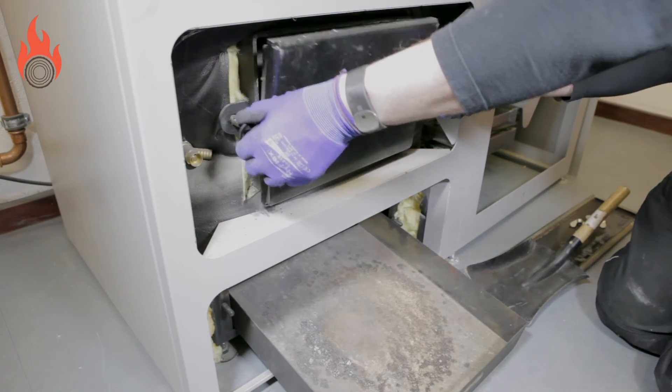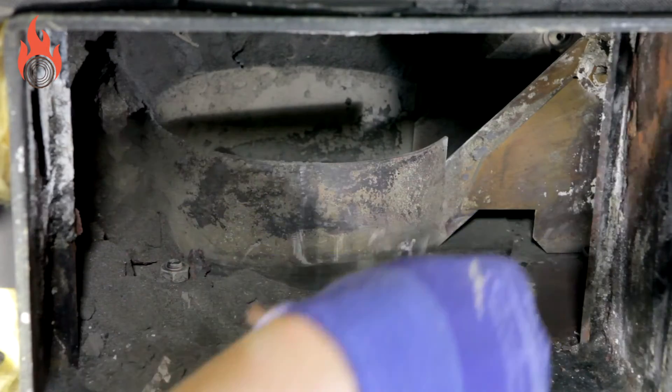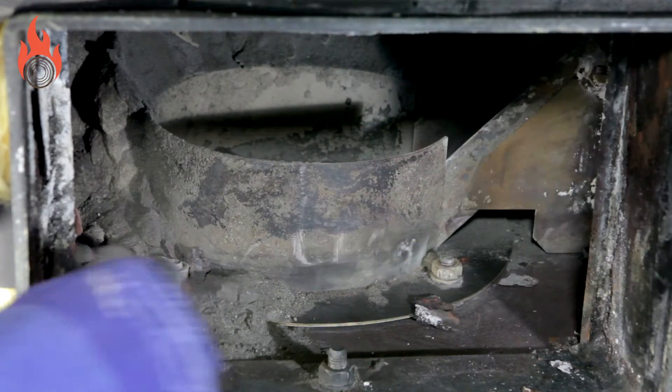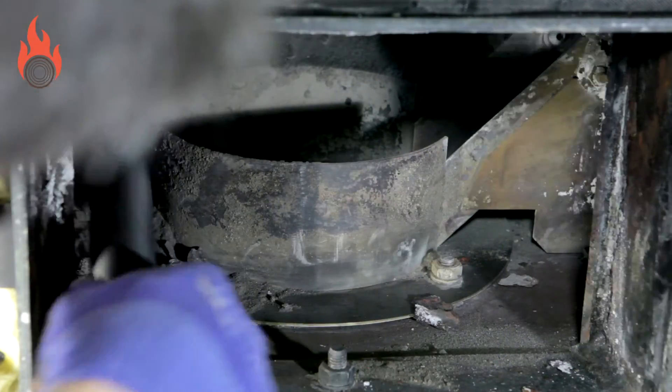Now open the upper cleaning door and keep the emptied ashtray under it. Remove the ash which remains around the burner using a vacuum cleaner. Also clean the area around the pellet chute. Check that the burner area is completely clean.